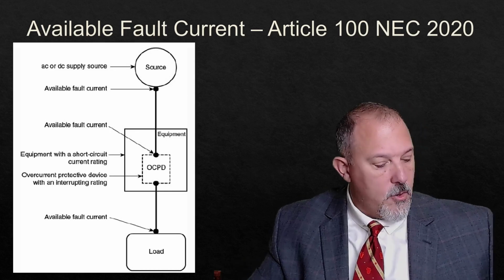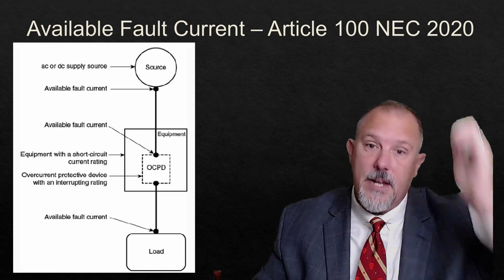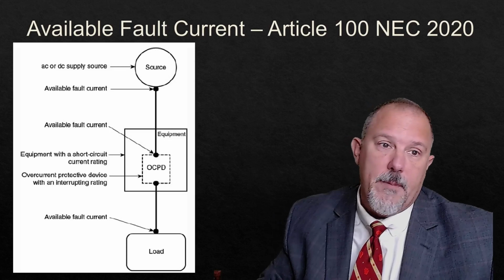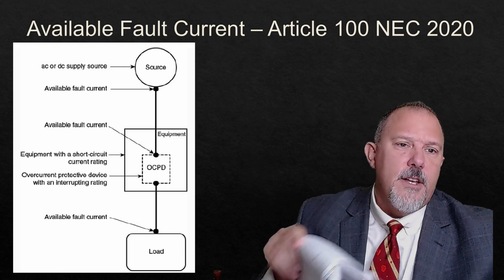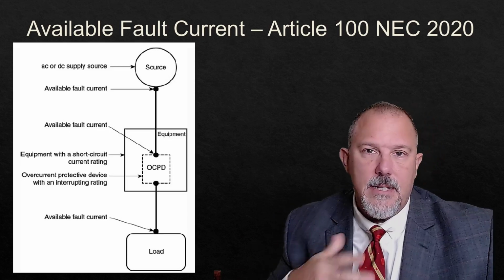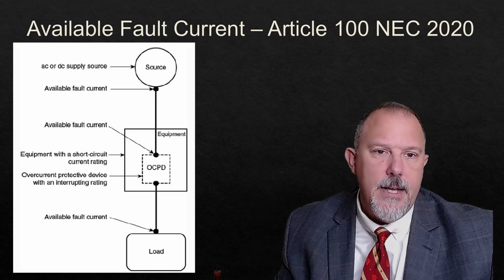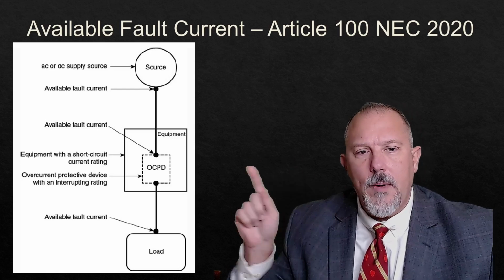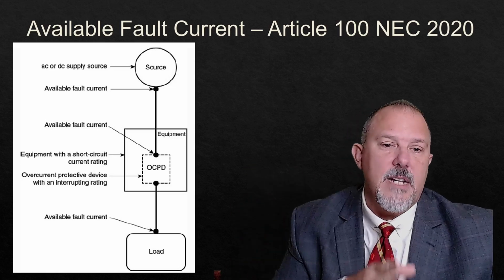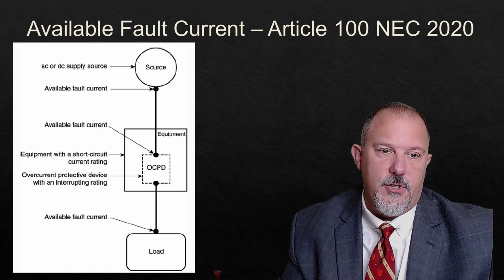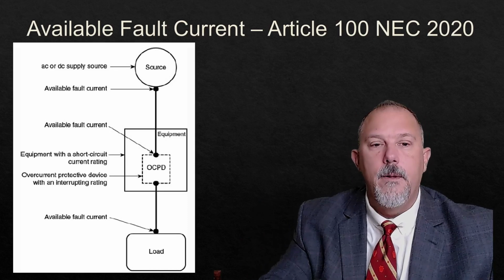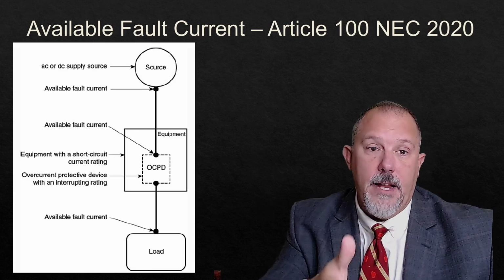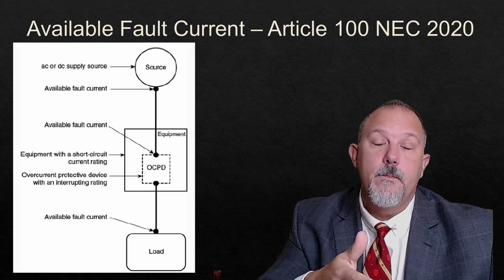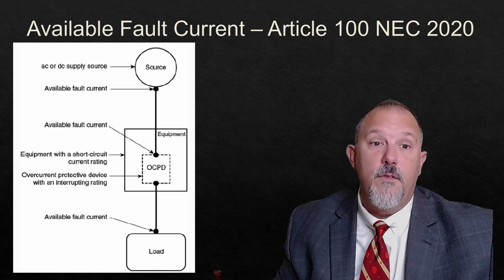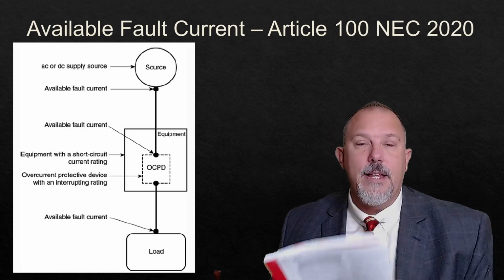Just going to take a look real quick. Yep. 70E and the National Electrical Code have the same diagram as well. So the source is AC or DC. It doesn't matter if it's AC or DC. And you'll look at the points. Like for an overcurrent protective device, what they tell us is that you should evaluate the interrupting rating of an overcurrent protective device with regard to its available fault current. And look, the available fault current is on the line side.